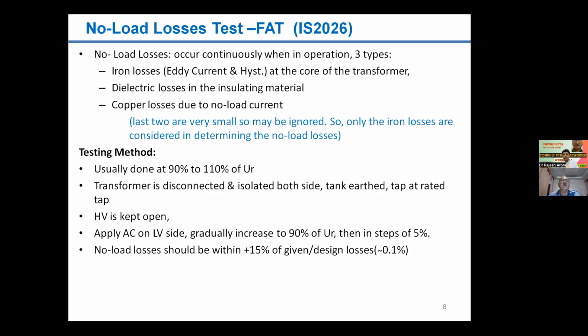How is it done? Usually at 90% or 110% of the rated voltage. The transformer is disconnected and isolated from both sides. The tank is earthed. The test is performed at the rated tap. As I mentioned, these are the practices, and slight variation may be there across different utilities, but I am discussing basically what we have studied from the standards I discussed earlier, and what you are practicing in BSES Rajdhani Power Limited, Delhi. So HV is kept open and AC voltage is applied on the LV side. Gradually, it is increased to 90% of the rated voltage. Then in steps of 5%, no load losses are measured. Next slide.